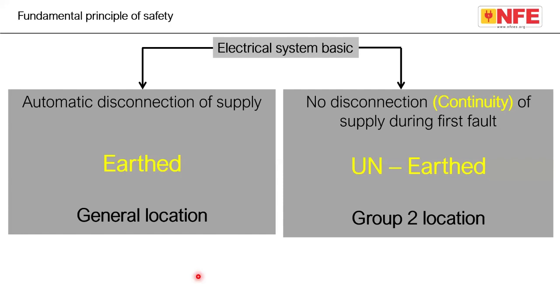Now, one of the most confusing subjects in the hospital location is earthed and unearthed supply. For general location, a TN-S supply must be used, which is called an earthed supply. That means the safety measure is protective equipotential bonding and automatic disconnection of supply. We will educate the participants of our biomedical course on all these measures in detail.